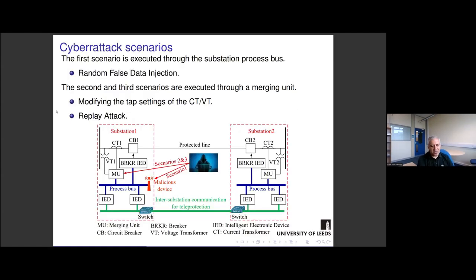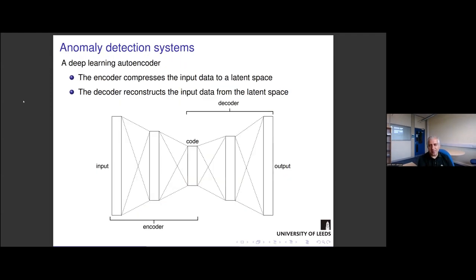So we consider three scenarios here. The first scenario is executed through the substation process bus. We assume that the attacker accesses the process bus remotely and then tries to inject random false data into the process bus to force the IED or protective relays to trip the transmission line. The second and third scenarios are executed through a merging unit by either modifying a tap setting of CT/VT or performing a replay attack.